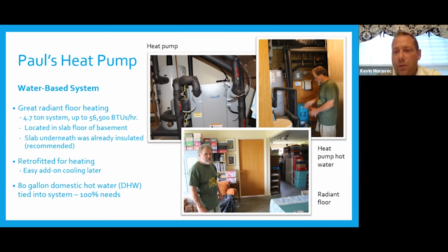We did redo the pumping system. We use a method called direct to load, which takes the hottest water directly off the heat pump, goes across a thermal expansion tank, which you can see in the top left photo. There's a buffer tank that sits there. The hottest water goes off of the heat pump across the top of that tank, and when there's a zone that calls for heat, that zone gets the majority of the capacity from the heat pump first, and then what the zone can't accept, the buffer tank takes.